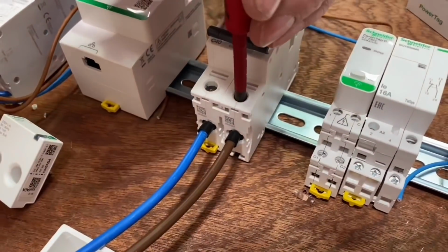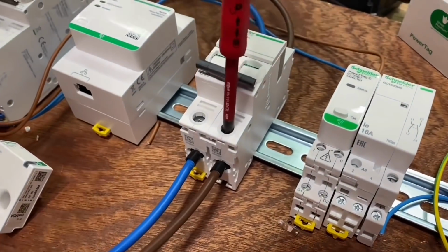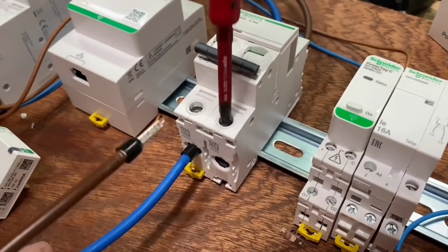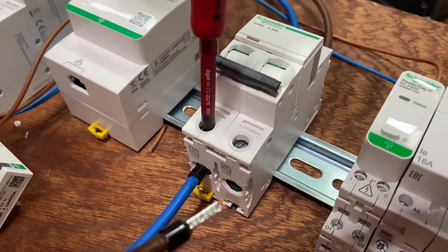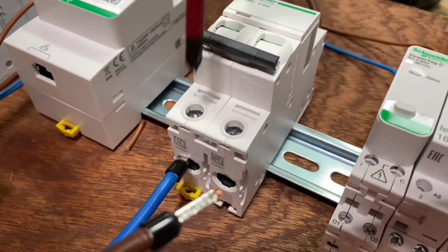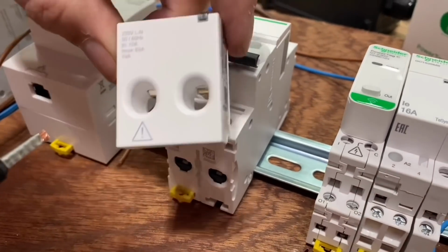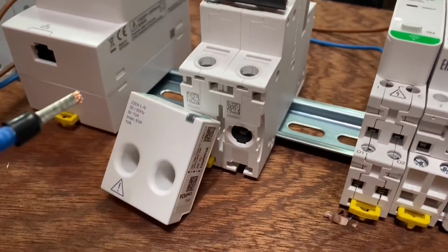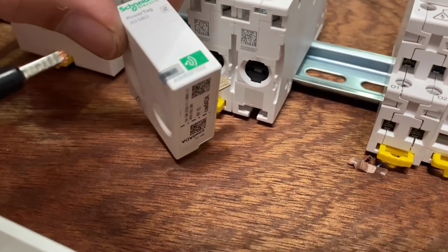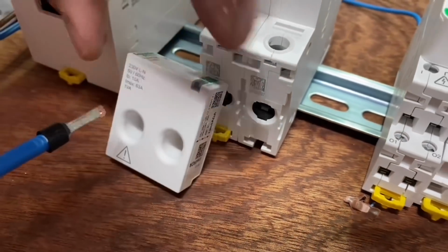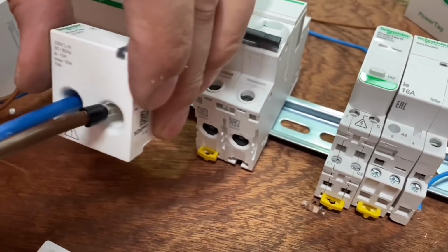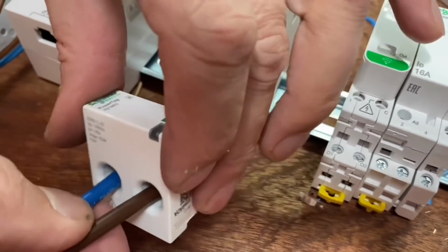So let's fit the PowerTag to this existing circuit breaker. It's dead easy to remove the conductors from the circuit - we're now inside the three-phase distribution board doing this. We don't see many double pole circuit breakers in the UK, but that's what we've got here. The PowerTag itself gets its power from the circuit it's connected to, with tabs for line and neutral.